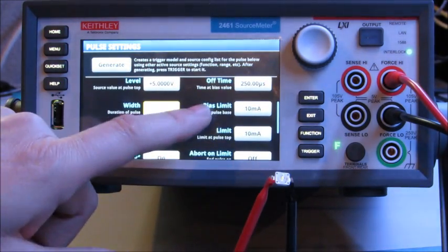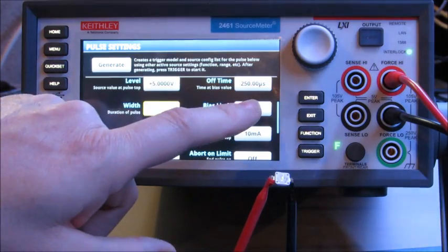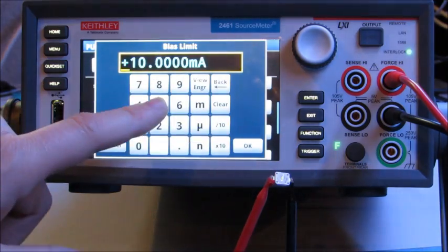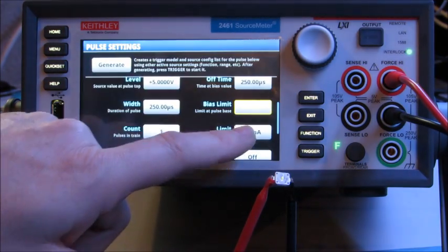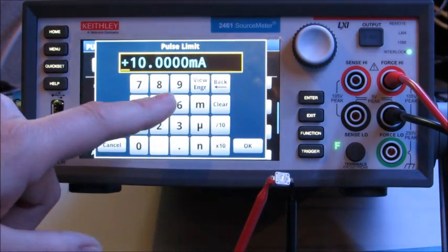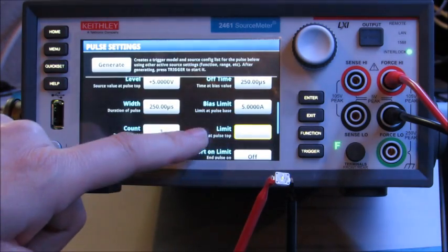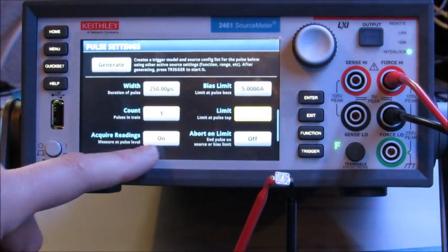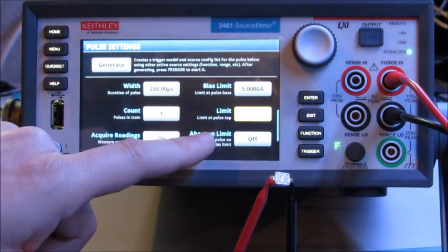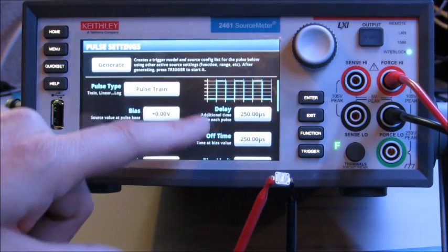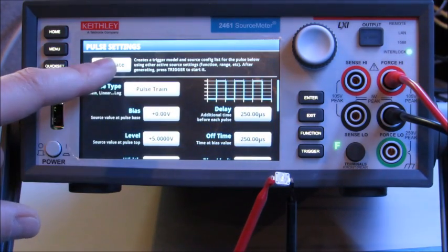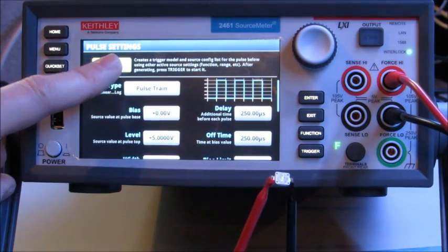And I'm going to set my bias limit and my limit to both five amps. I'm going to leave acquire readings on and abort on limit off. So now I just need to generate this test. So let's hit the generate button.